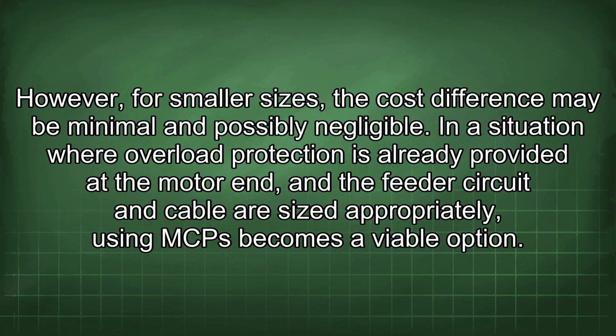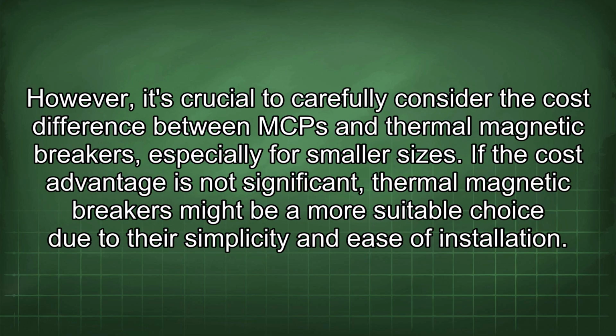In a situation where overload protection is already provided at the motor end, and the feeder circuit and cable are sized appropriately, using MCP becomes a viable option. However, it's crucial to carefully consider the cost difference between MCP and thermomagnetic breakers, especially for smaller sizes. If the cost advantage is not significant, thermomagnetic breakers might be a more suitable choice due to their simplicity and ease of installation.